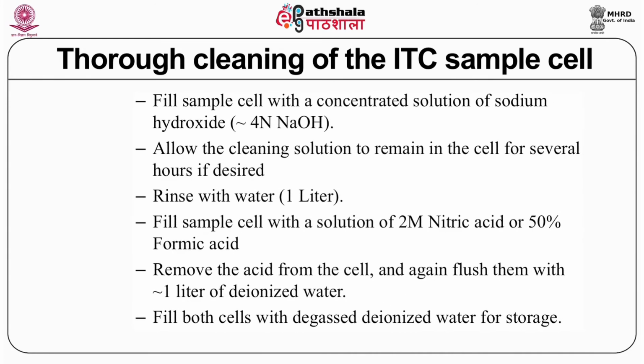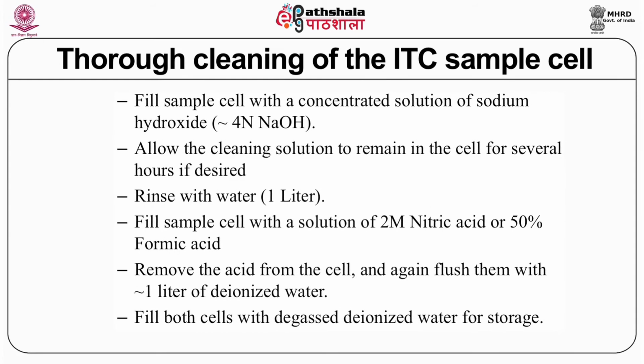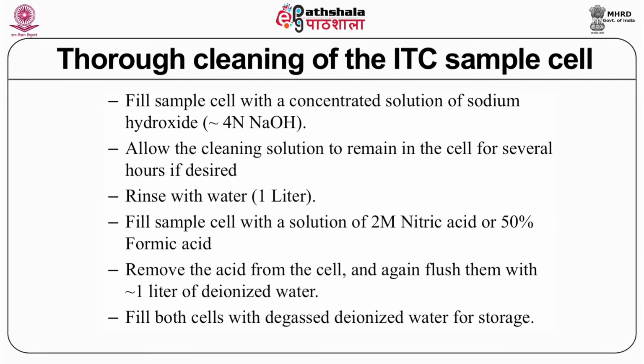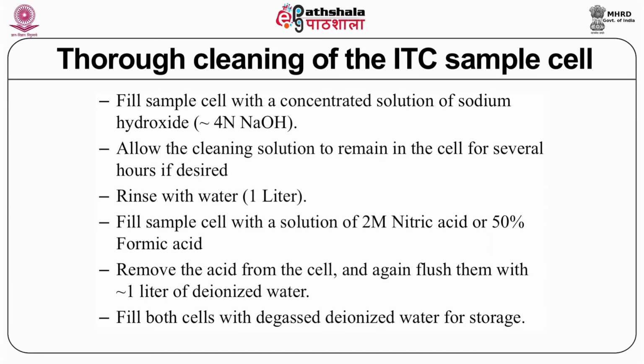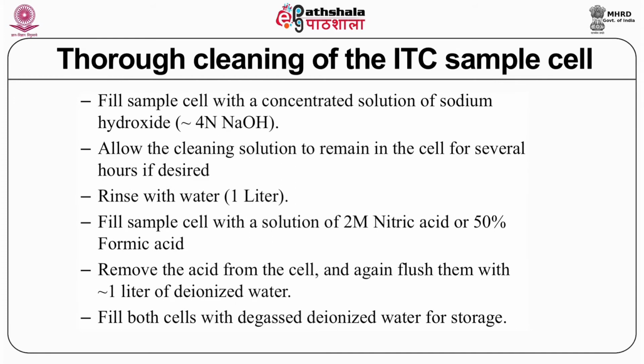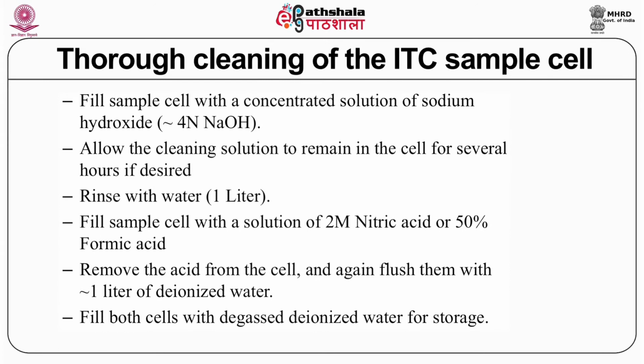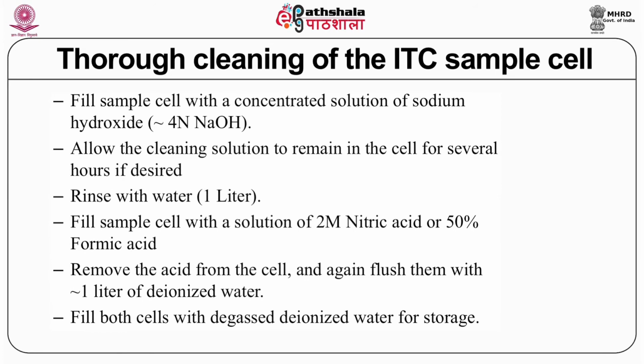Then of course, once you remove with acid and base, then again remove with nitric acid, wash it again, and then both the cells have to be filled with degassed, deionized water. The degassing is important so that there is no dissolved oxygen in the water, and also deionized water, because ions contribute a lot to the charge, and therefore they also react.